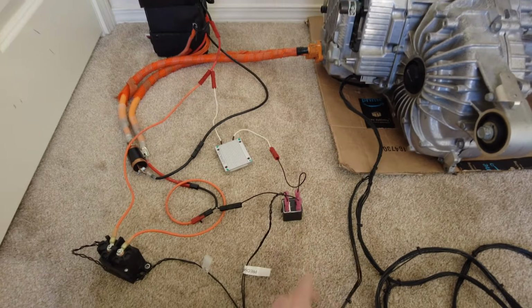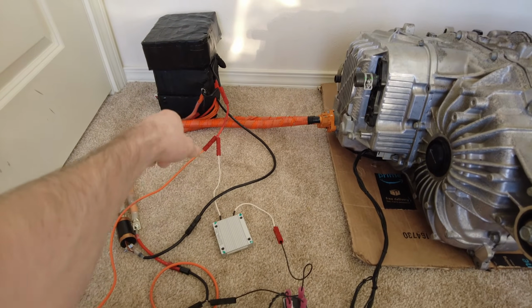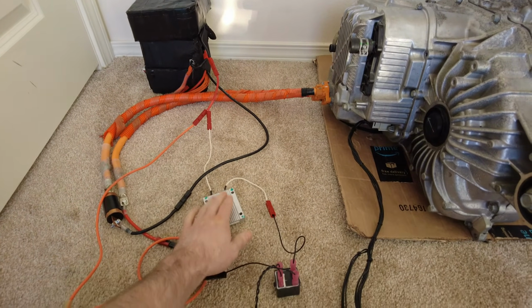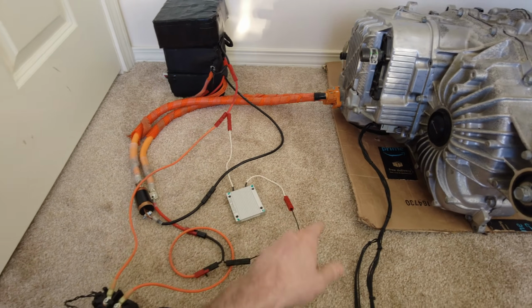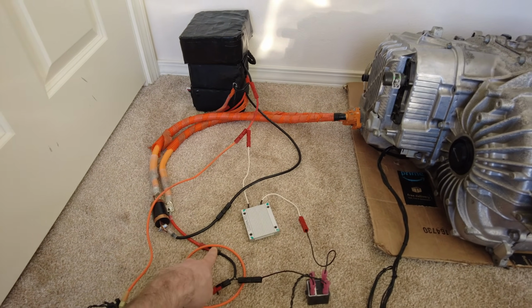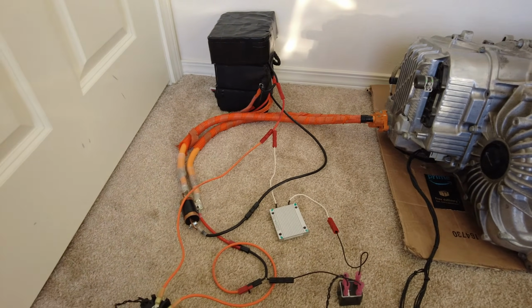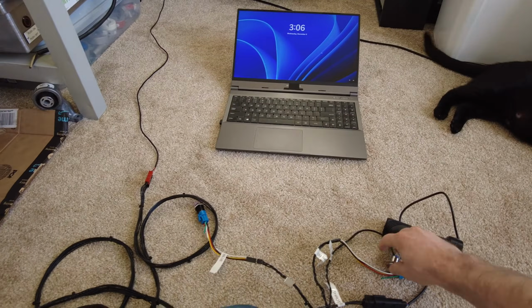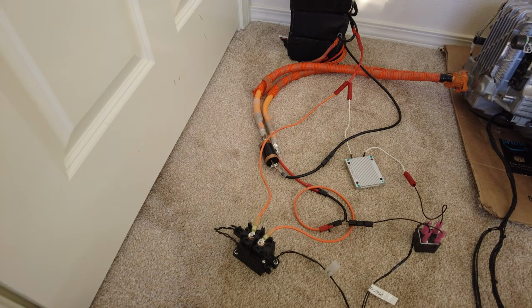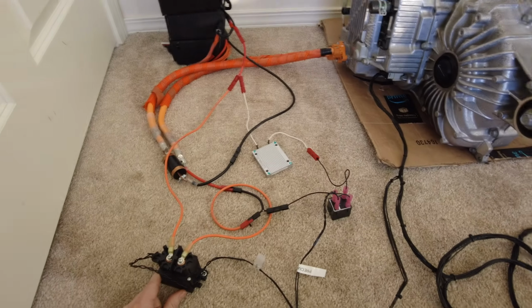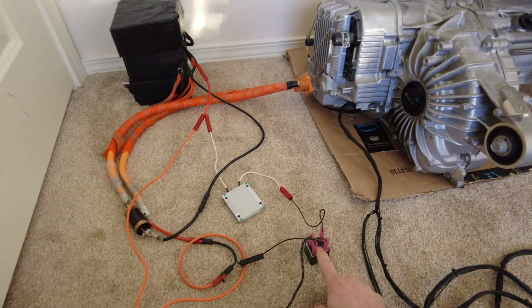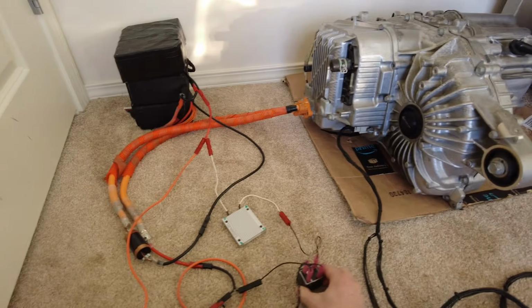There we go, so now it's pre-charged. Basically it took positive battery through the resistor, which limited the current, and charged the positive side of the inverter's capacitors. When we hit the start button, assuming it's pre-charged, it should close the main contactor. And there we go, it opened the pre-charge relay because it's not necessary to keep this closed.